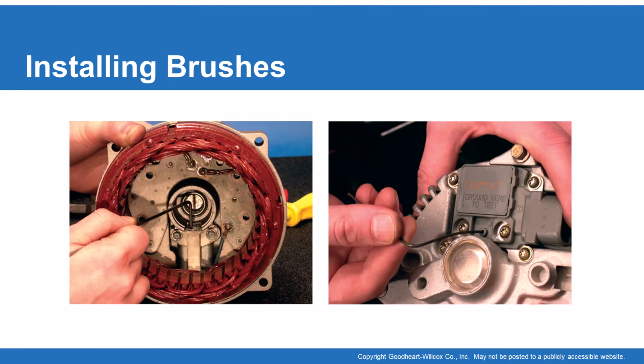Now, installing the brushes, you can see here, we're going to push those in, and usually there's a lock that you can stick a small piece of wire, or something thicker than wire, through to lock the brushes in. Most often when you're replacing these, they come with that lock installed, and then you put in the brush pack and pull out the lock, which allows the two brushes to slip forward and press up against the slip rings on here, which is critical. And keep in mind that often those carbon brushes may not be perfectly round with the slip rings, and it takes a little bit of driving to wear them in so that you get nice smooth contact over the complete surface.